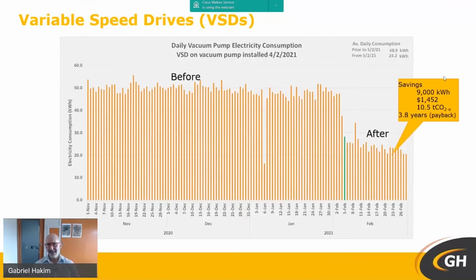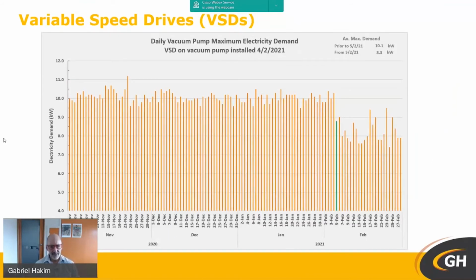So we worked out that there's a saving there of around 9,000 kilowatt hours and almost $1,500, and that's a 3.8-year payback before any grants or whatever. So that's a really good example of how these things can work. The other thing is that the VSD on this vacuum pump has reduced the demand charges as well.